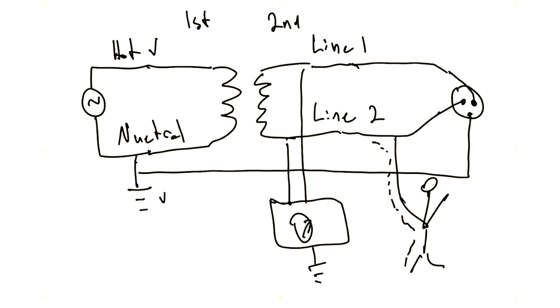However, if you were to touch something that is at line potential 2 with that hand and then touch line 1, something at the potential of line 1 with the other hand, now you are receiving a shock. So that is what would need to happen in order for electrical shock to occur. You would need to have a two-fault condition, right? Two faults, both a fault with line 1 and a fault with line 2. Okay, let's take a look at another example.